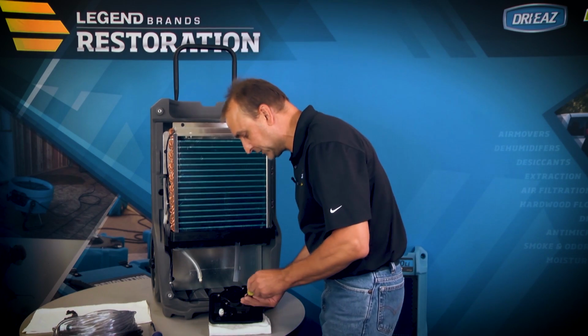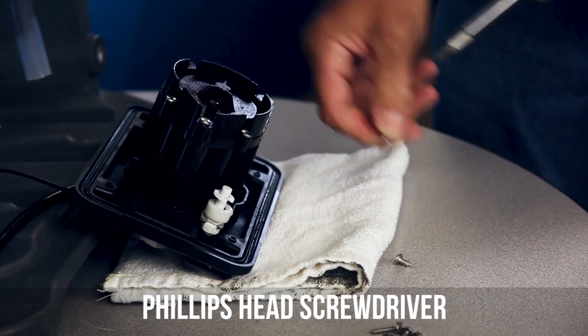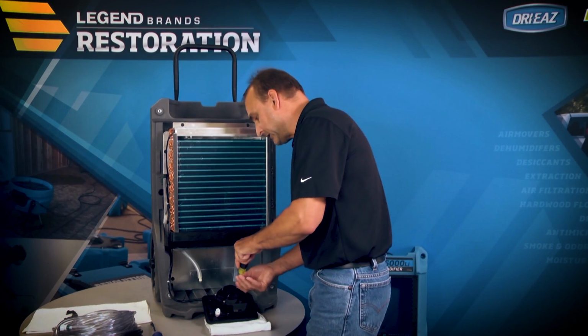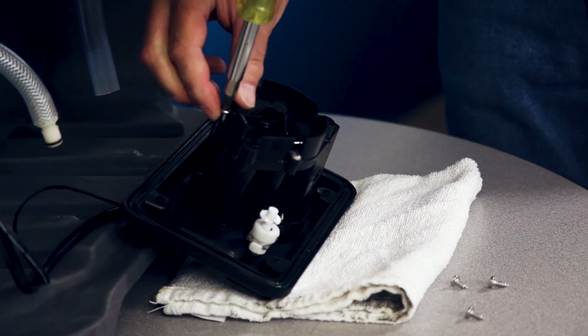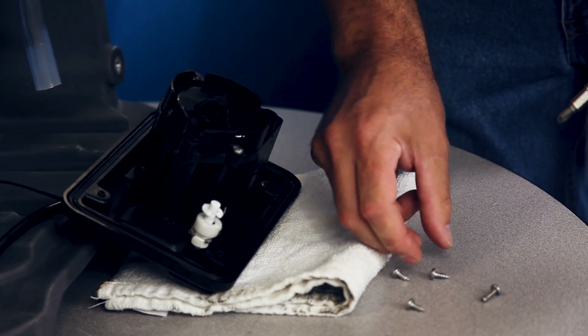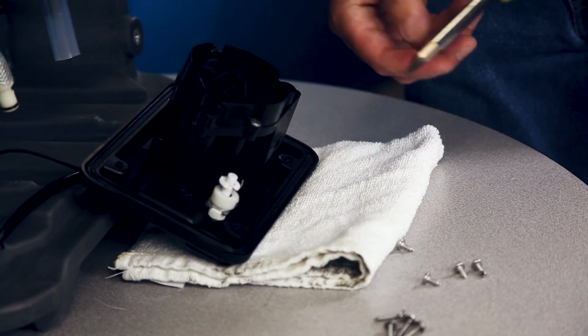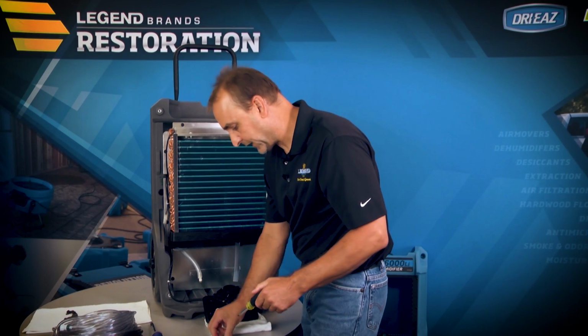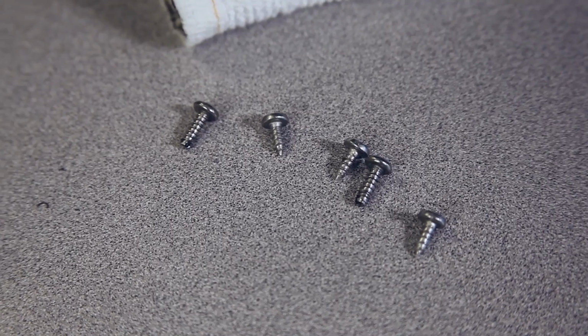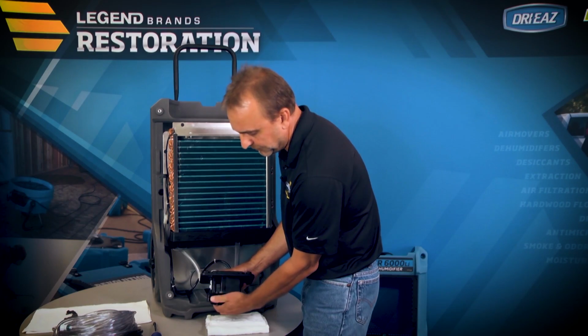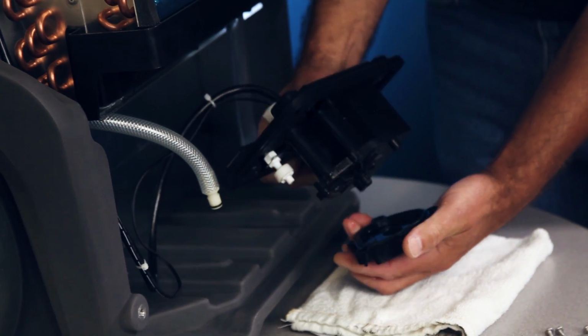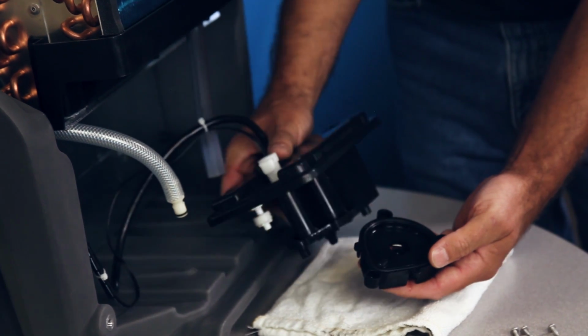There are 5 Phillips head screws on the bottom. When removing the screws, you'll notice 3 of the screws are short. They are on the 3 corners. And the 2 longer screws are just inside of the output. After the 5 screws are removed from the condensate pump inlet cover, turn the condensate pump back over, give it a little wiggle and a pull, and the inlet cover comes off.